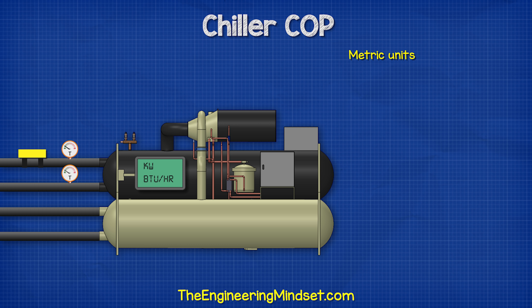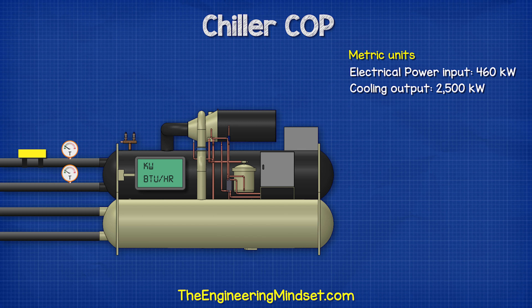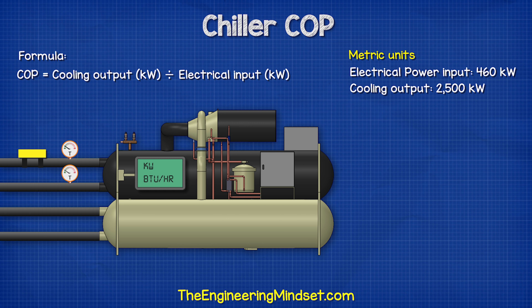Coming back to the COP and considering the metric units first, we can see from our data gathering that this chiller is demanding 460 kilowatts of electricity and is providing 2,500 kilowatts of cooling. Using the formula COP equals kilowatts of refrigeration divided by the kilowatts of electricity, if we drop those numbers in, we get a COP of 5.4.